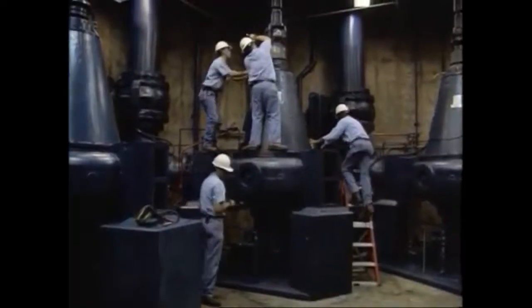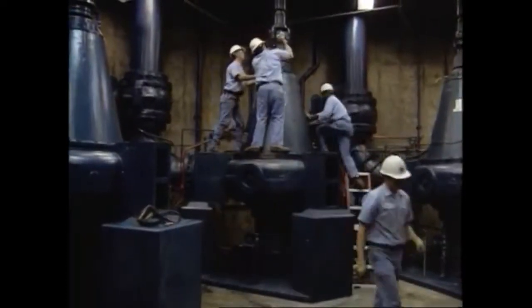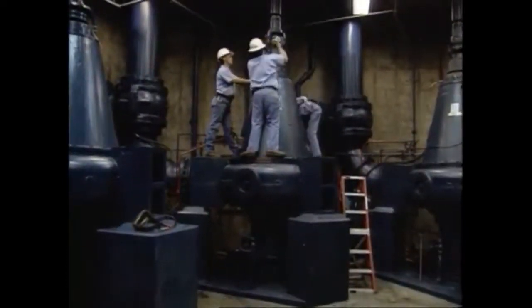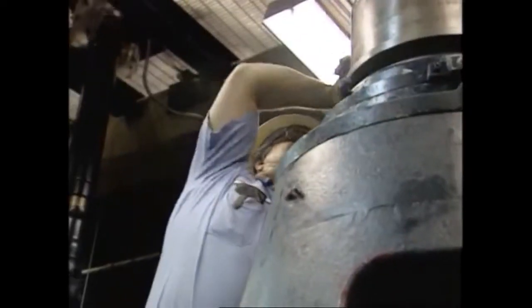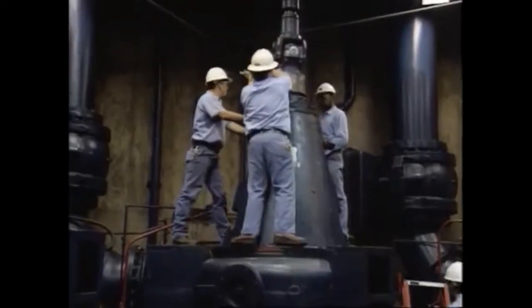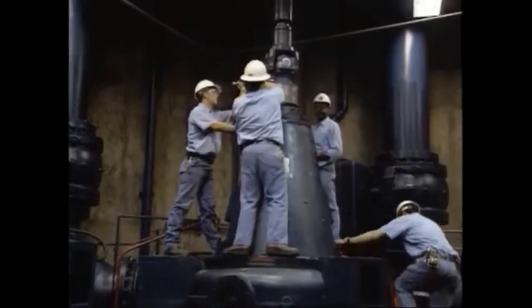Initially, mechanical seals are much more expensive to install in a pump. However, this cost is gained back in the form of lower operating costs over a period of time. The limitations of mechanical seals are the high initial cost and the need for a competent mechanic for installation. In addition, when the seals fail, the pump must be shut down. With some types, the pump must be dismantled to repair the seals.